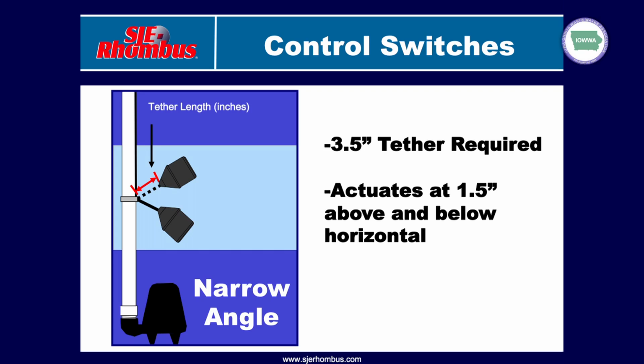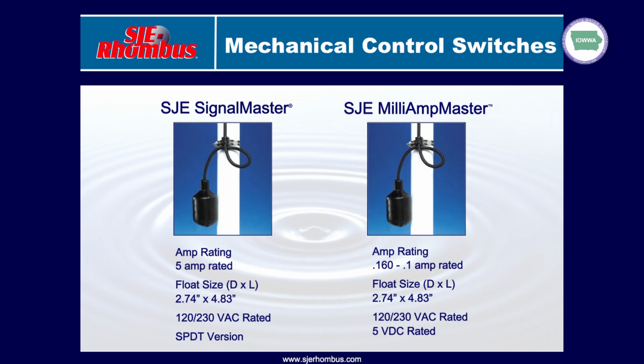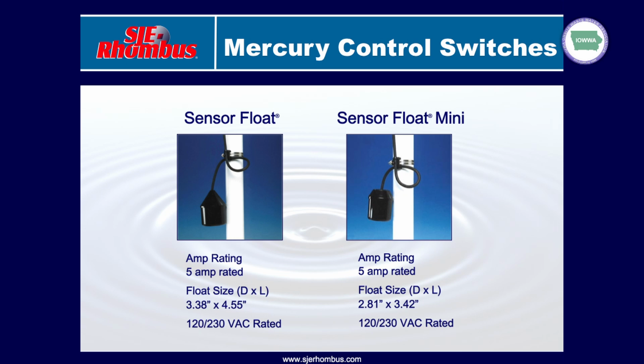All we need is 3.5 inches, so I would encourage you on a control switch with a high level alarm or a control panel, limit it to about 3.5, 4 inches of tether coming off that discharge pipe of the pump or the float tree. And then actuation on a control switch, most of the control switches that we manufacture are going to be narrow angles, so we're going to have 1.5 inches above or below horizontal for the activation point. There are some other float switches on the market, control switches, that are going to be a little less than that, maybe 1/2 inch above or below horizontal. And then just a couple of different control switch mechanical options that we have. Same thing on the control switches, we also offer a mercury version. And I'm jumping right through those.